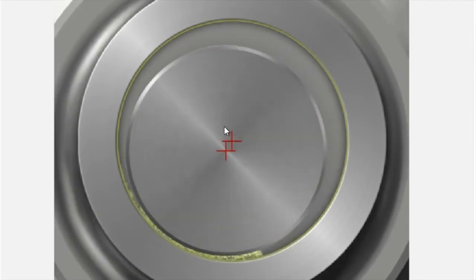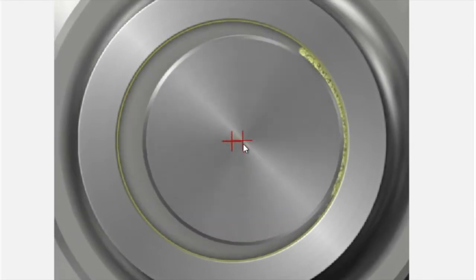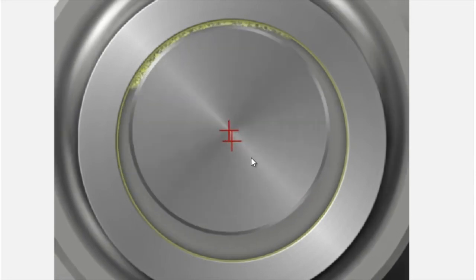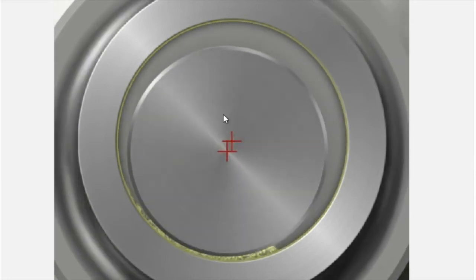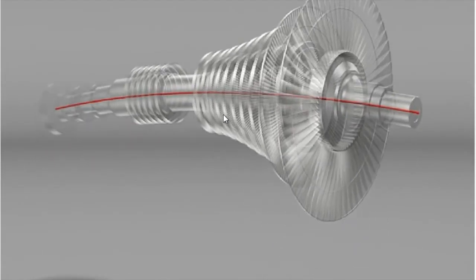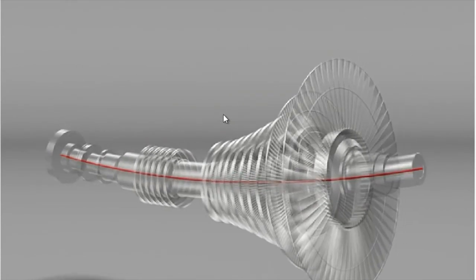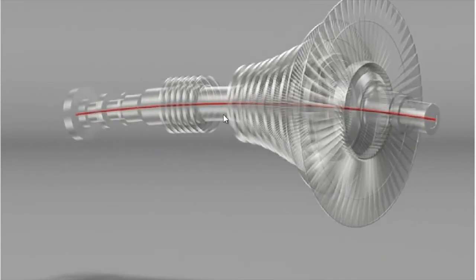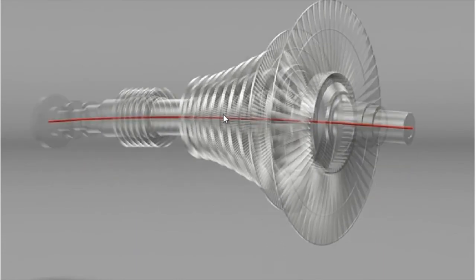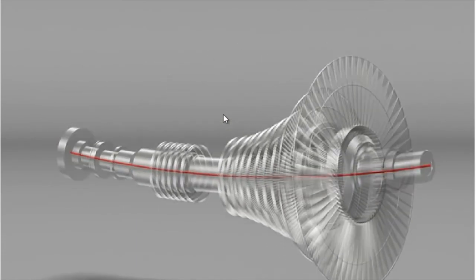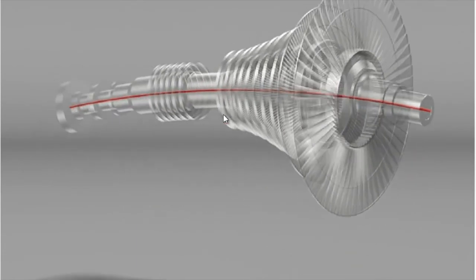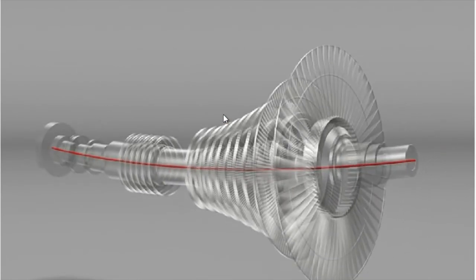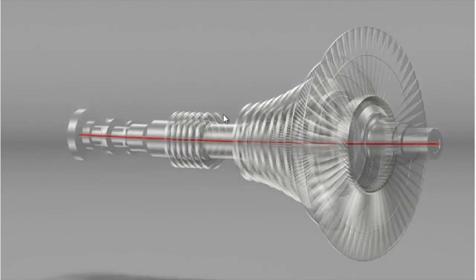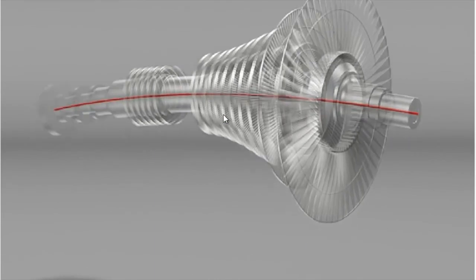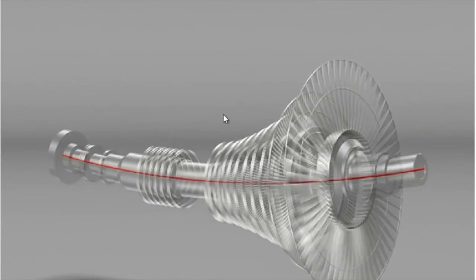But this is the sort of thing we'd like. We want to know, in essence, what the shaft is doing, what the center of the shaft is doing. Because there are other faults, in addition to unbalance and misalignment and preload and these sorts of faults, we're interested in the rotor dynamics as well, particularly as we go through the critical speeds. So in this instance, exaggerated, that's the motion at the first critical, let's say.